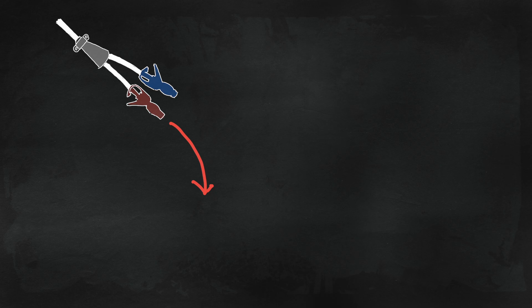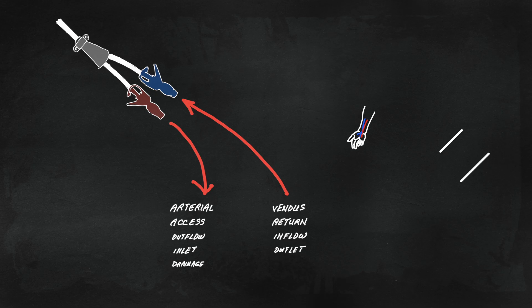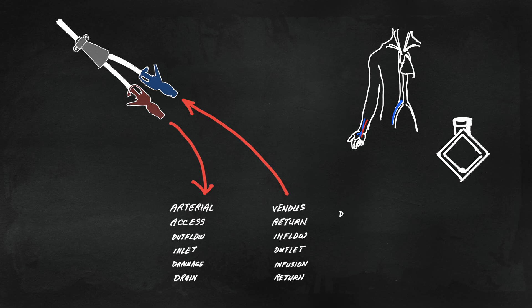A typical naming scheme in dialysis is arterial and venous ports, which makes sense with arteriovenous fistula or graft access, but not so much with catheter access where both drainage and transfusions are from a vein.